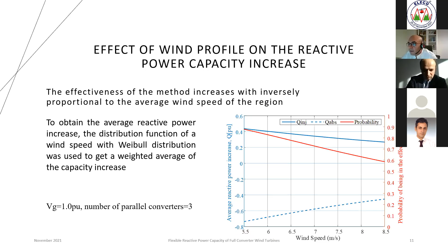As conclusions, as a summary, a new control method with parallel converters of full converter-based wind turbines to increase the reactive power capacity further has been proposed. With this method, the total reactive power capacity of full converter turbines which use parallel converters can be significantly increased for both directions of reactive power flow. This may lead to a reduction or removal of reactive power sources installed in wind farms or in locations close to the applied wind farm.